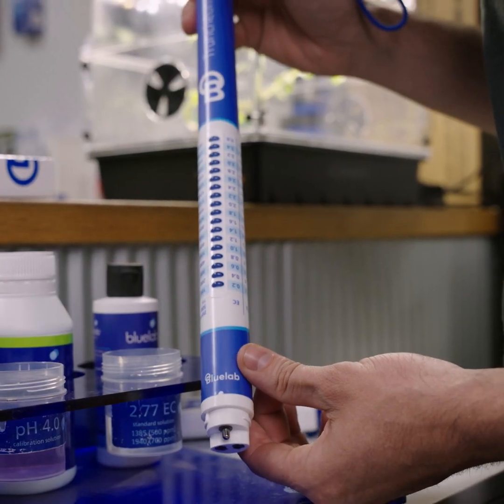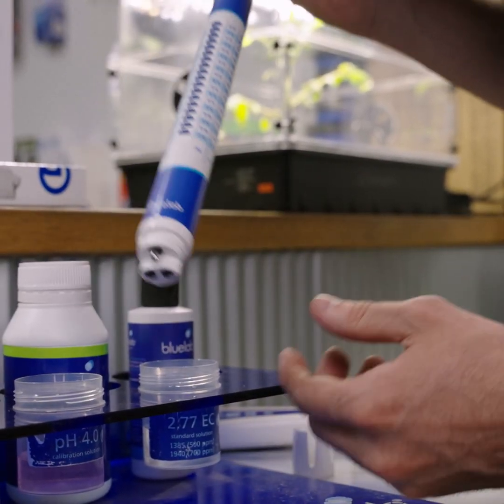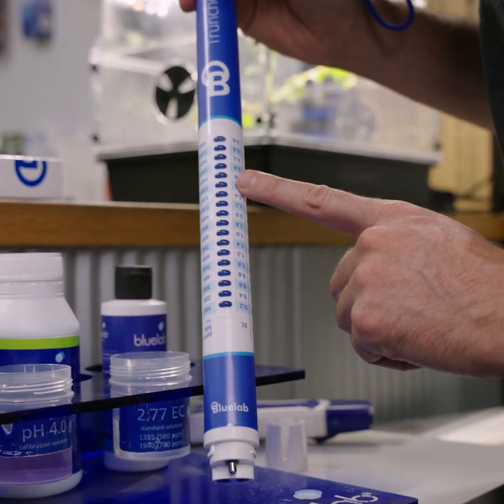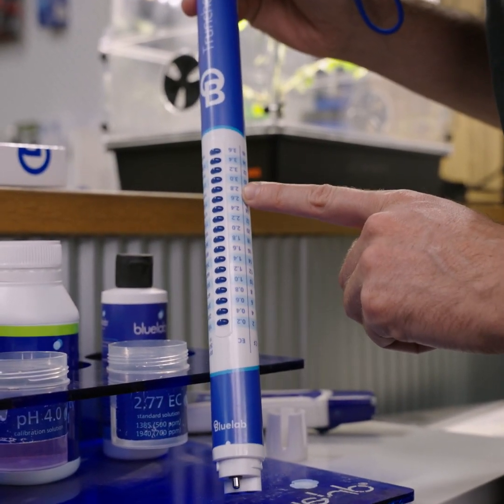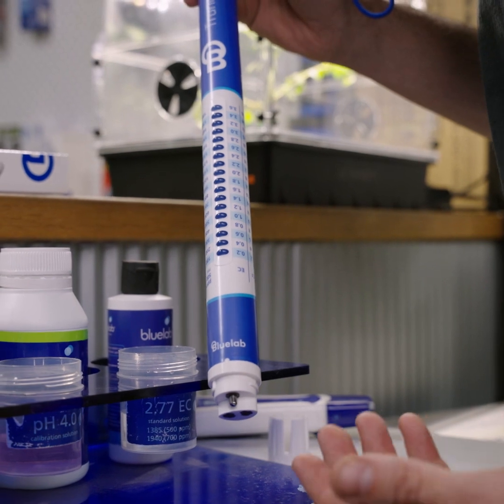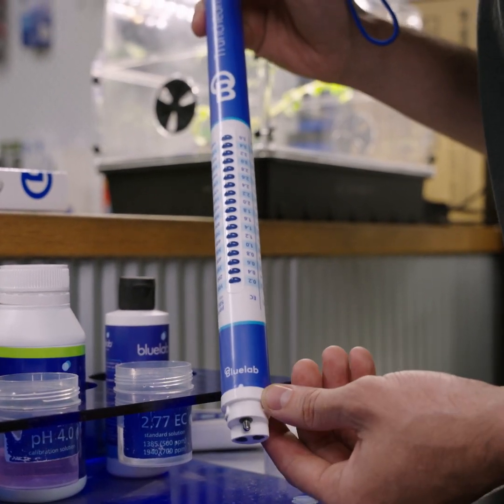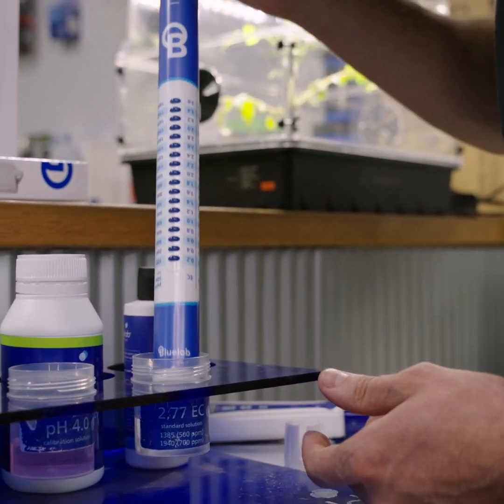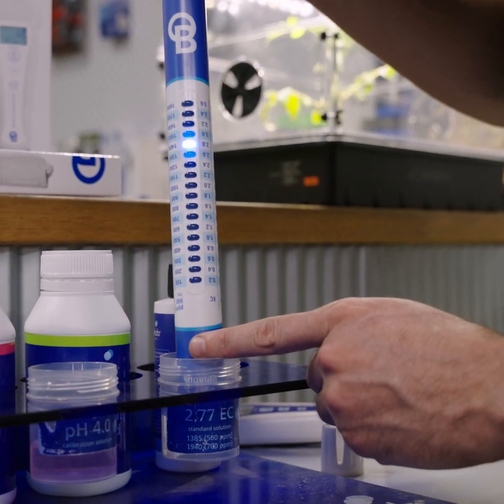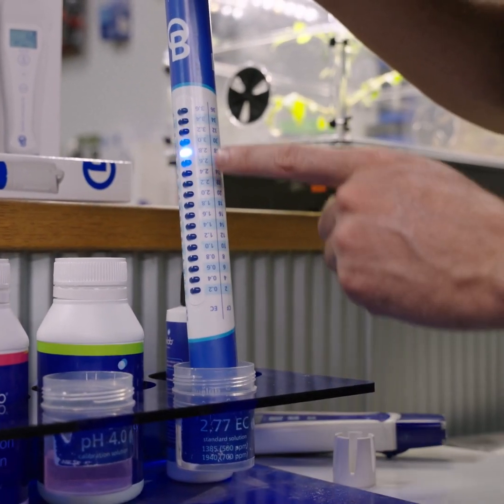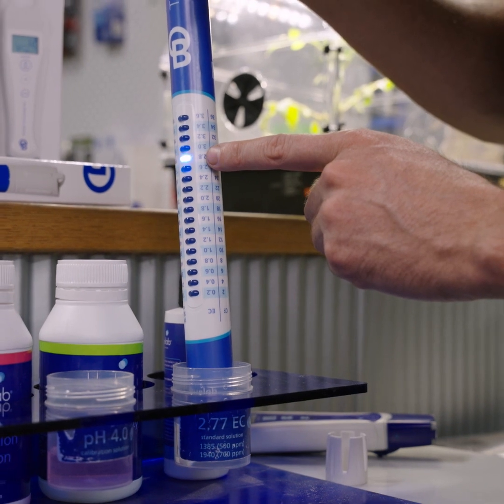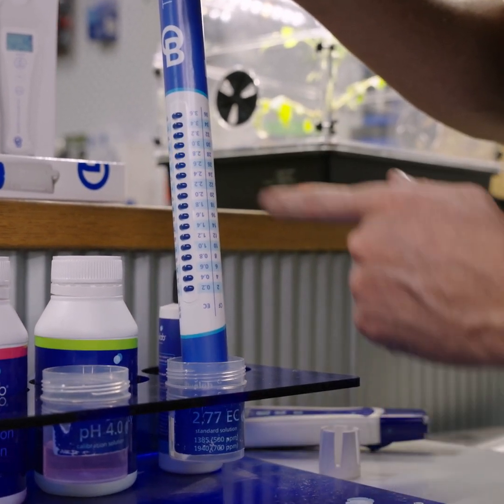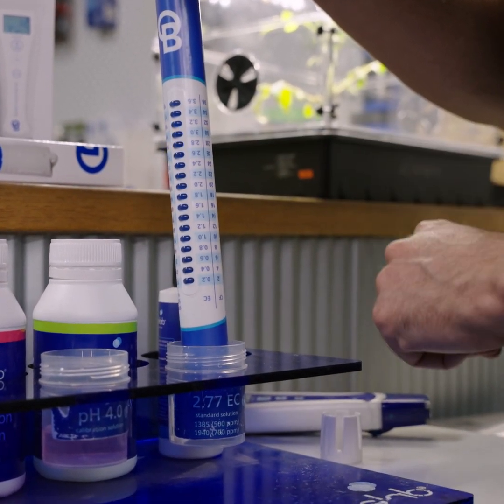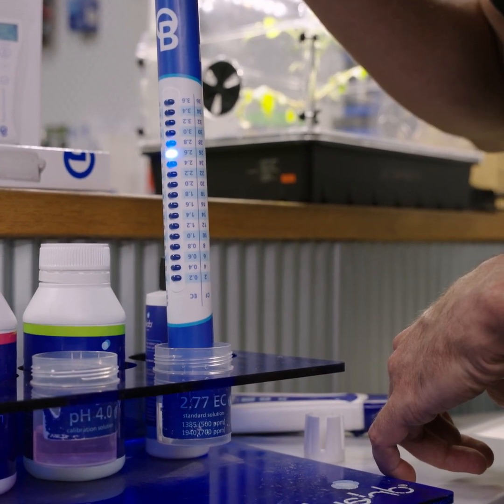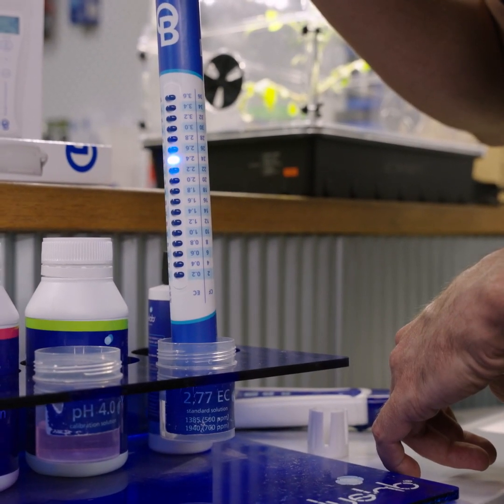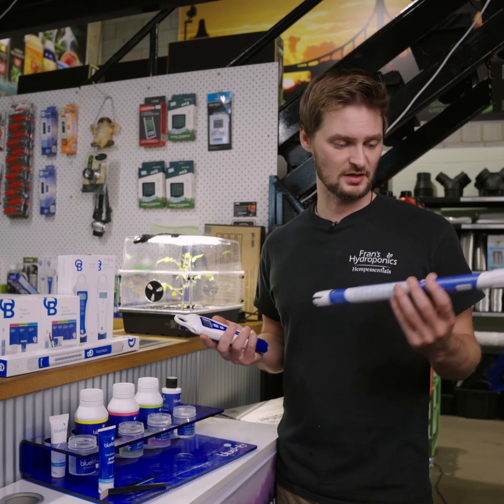So we're just going to put it into the 2.77 solution, and hopefully this will flash up at about 2.8, and that way we know that it's reading correctly. Doesn't need to be calibrated, just need to test that it's reading correctly. So this is some new solution, and on the EC it's jumped straight to 2.6 and it's flashing between the two. That's very common, but it's pretty much on 2.8. So that's reading correctly. I'm showing you 2.8. So that's how simple it is.